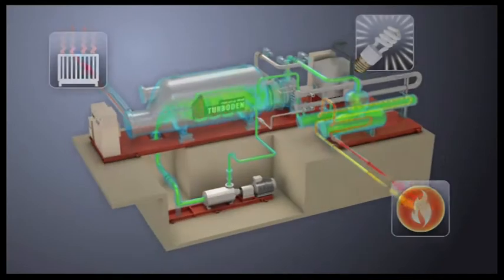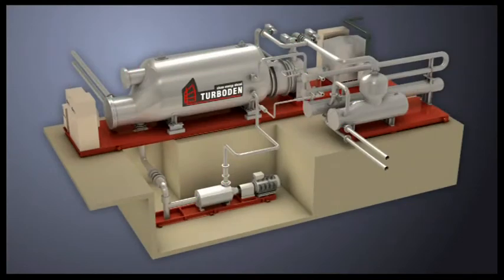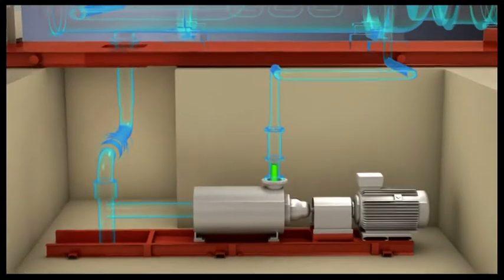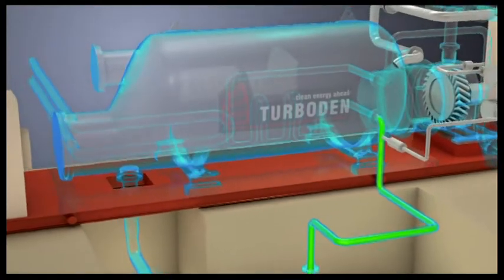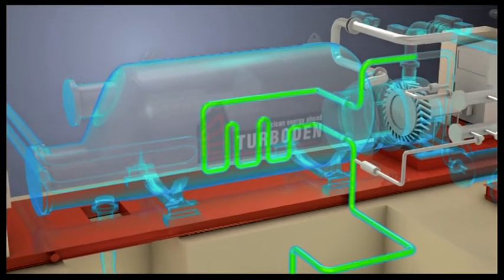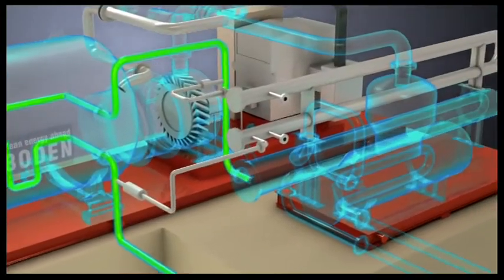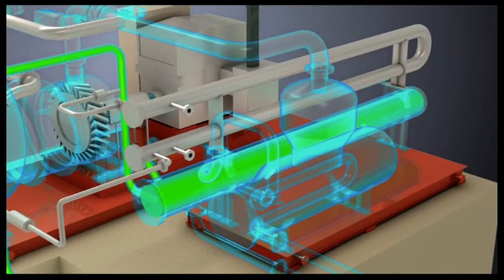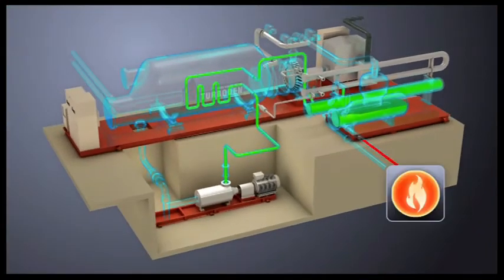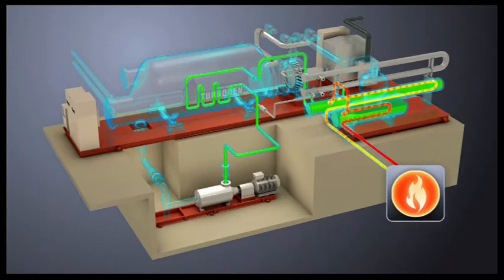Let's take a closer look at how a co-generative ORC Turboden system works. The organic fluid in liquid form is fed into the closed loop through a pump. It then runs through the regenerator coil where it undergoes initial heating. The fluid is then conveyed to the preheater and into the evaporator. At this point, the thermal oil in the boiler increases the fluid's temperature until it reaches evaporation point.